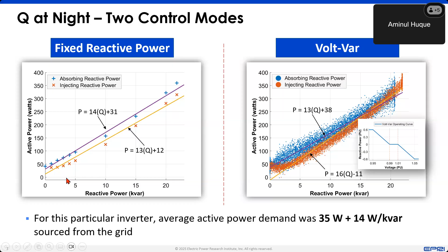Then more recently, we tested a new inverter, which is actually IEEE 1547-2018 certified, or 1741 SB certified. If you're familiar with the distribution side requirement, that's the requirement. And this particular manufacturer offered this capability again, and they have a white paper or some description on their website that explains how to do it. So again, we had to find out what the setting is and how to activate it. This particular inverter, our OEM calls it reactive power for 0 active power. The names are all over their own description since it's not defined in the standard.